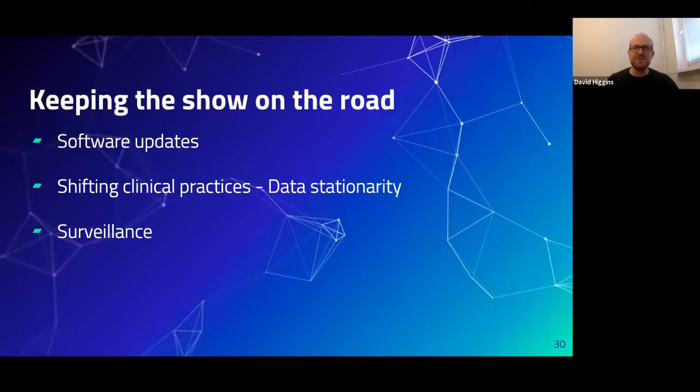So for minor updates, it's usually possible through negotiations with the regulatory body to do a real update, to really push something without doing a clinical trial. But you have to specify what's minor versus what's major in terms of updates to your code, in terms of retraining the model, these kind of things. And how you do it is also relevant. I mean, there is basically a growing trend towards cyber attacks, and your update mechanism could also be hijacked, and you need to be really careful about that.